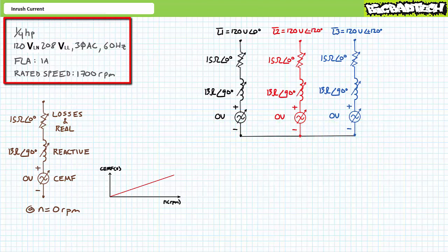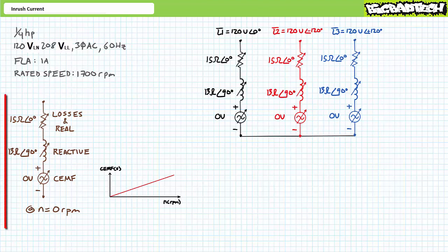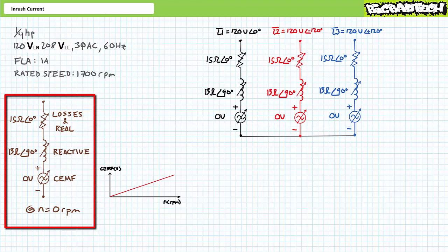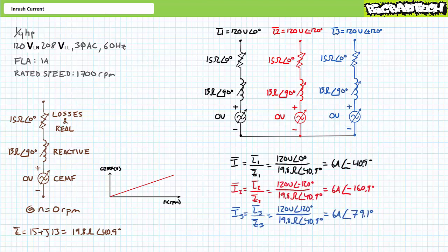Let's examine how rotational speed and the resultant CEMF influence inrush current. Consider a quarter-horsepower motor designed to operate using 208-volt line-to-line, 120-volt line-to-neutral, 60 Hz three-phase AC in a Y configuration. At rest, the winding can be modeled as a variable resistance of 15 ohms, a reactive component of 13 ohms, and zero counter-electromotive force. The total impedance is roughly 19.8 ohms at an angle of 40.9 degrees. Upon closure of a full-voltage starter, each winding experiences full voltage, and application of Ohm's law demonstrates each winding draws roughly 6 amps, lagging each phase by a relative 40.9 degrees. This is the inrush phenomenon.